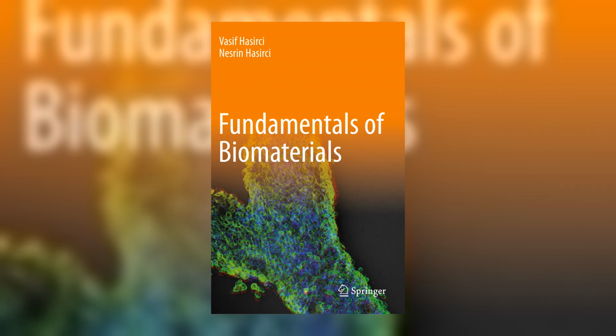10993 battery. This section explains why a polymer implant's degradation products, rather than the solid itself, are the object of safety certification, and where Part 13 sits in the structure of the standard. The thing you certify is the set of degradation products. What hydrolysis and enzymes release into tissue over months is the real exposure. Safety is a property of the trajectory rather than of the pristine solid. You must name each fragment and measure how much of it appears.